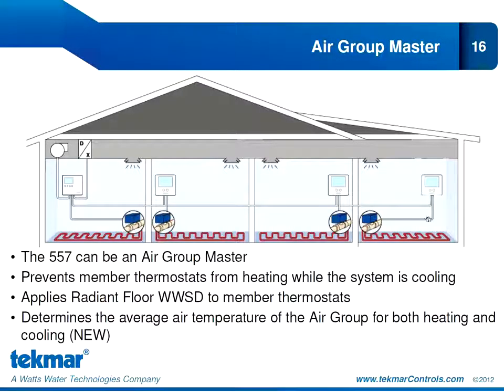You may be familiar with the term air group master. If you are not, an air group master controls the forced air heating and cooling for a group of radiant floor heated zones. So we have shown here one zone that has the 557 thermostat controlling this equipment, and we have 3 other zones that all share the same ductwork. And each zone would operate its own radiant floor.